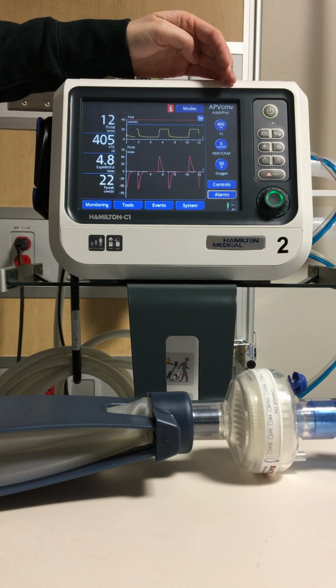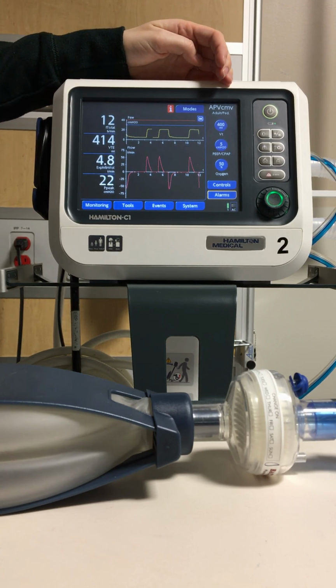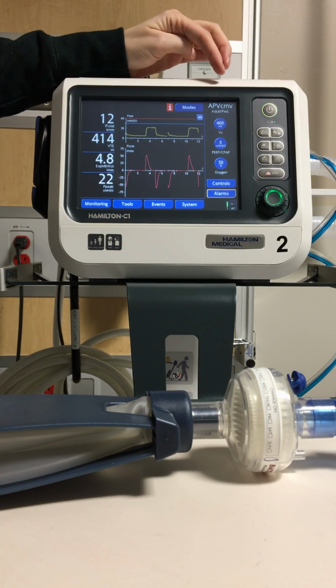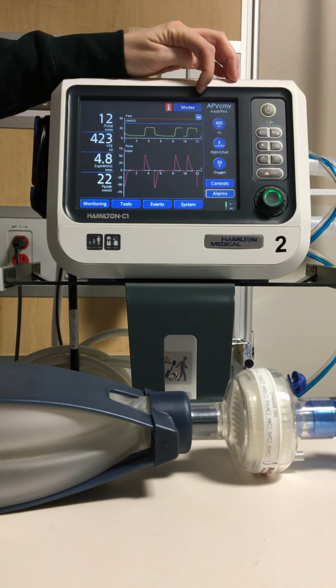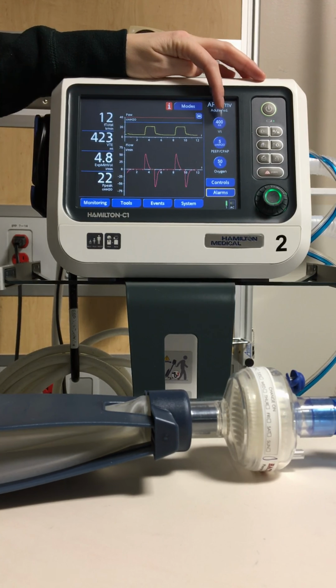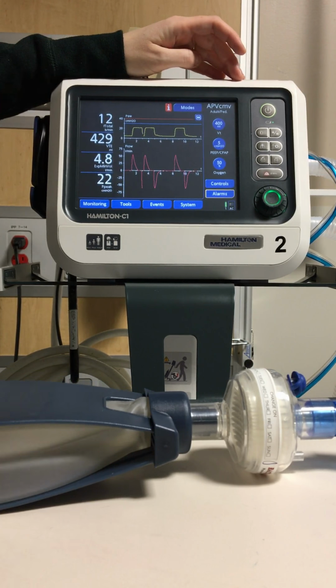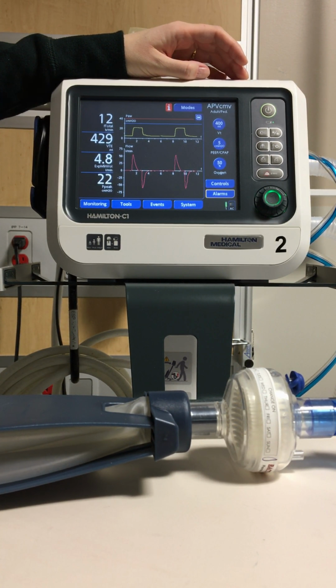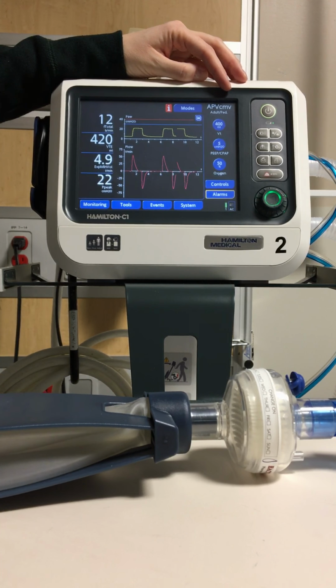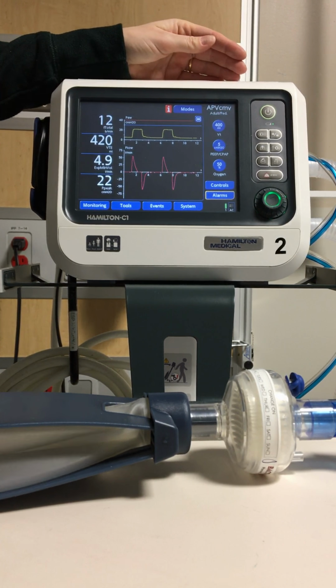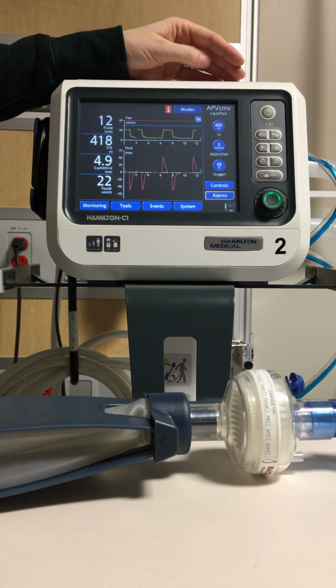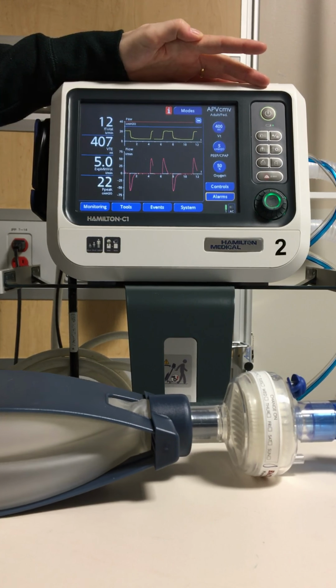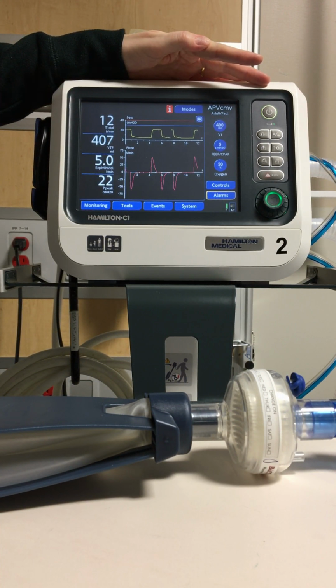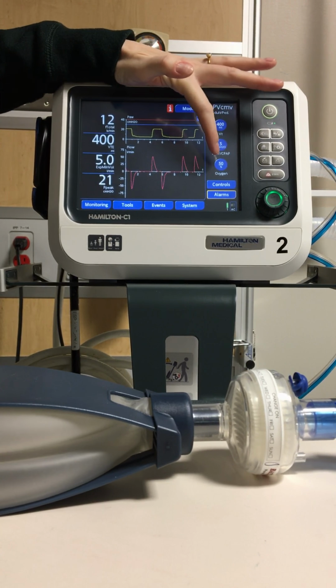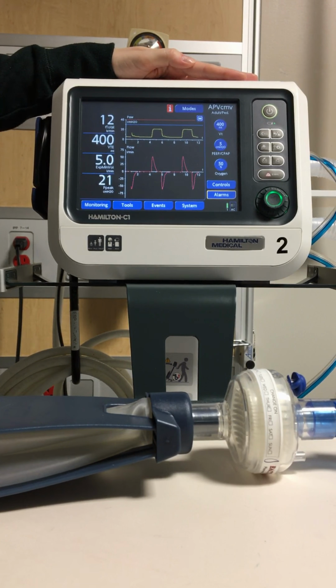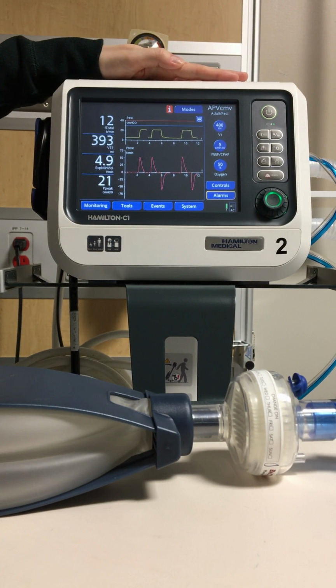On the right-hand side of the screen, you'll see the actual settings. These are not monitored values, these are settings. So you will see at the top the mode that the patient is in, and I'll talk about mode in person. Next, you will see the volume on this particular mode because it's something that we set. APV CMV is a very common mode that you will see in emergency. Next, you will see the PEEP, positive end expiratory pressure, commonly set at 5, but often higher in patients who require a little bit more recruitment and oxygenation. And lastly, the oxygen. That's their fraction of inspired oxygen as a percentage.